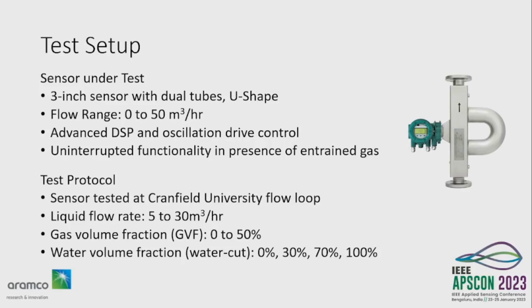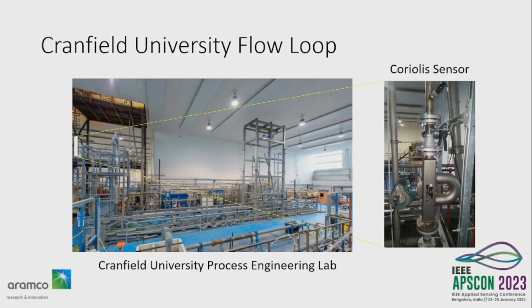We took the sensor to the Cranfield University flow loop in the UK and tested it under various conditions of gas entrainment. The liquid flow rate was varied from about 5 to 30 meter cube per hour, and the gas volume fraction within the liquid was up to 50%. We also varied the liquid mix of oil and water, the water volume fraction, or water cut as we call it in the oil industry, ranging from pure oil to pure water, so the liquid density was also varied in the test. That's a picture of the process engineering lab. At the far top left corner, on the first floor level, is where the sensor was installed in the flow loop to test it.